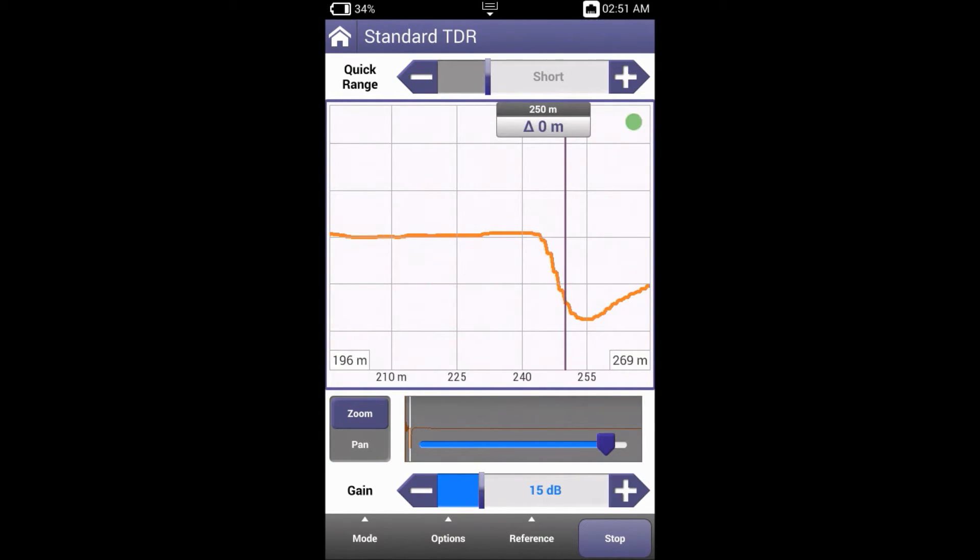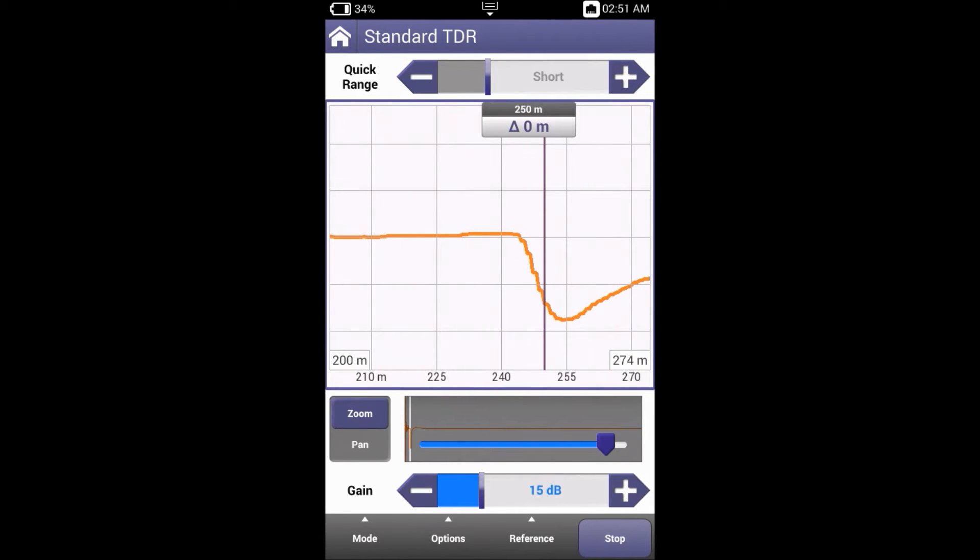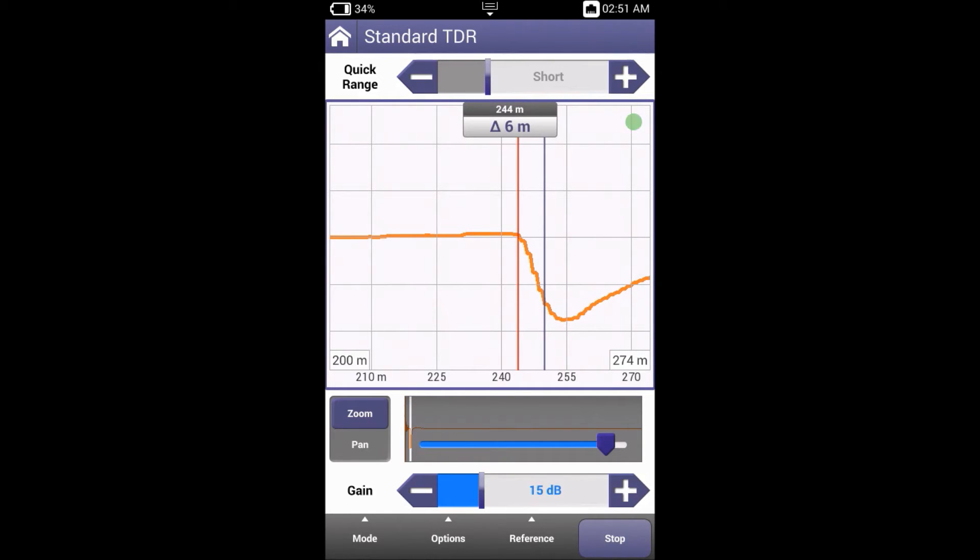To see this difference, we'll first zoom in and then press the marker button. Here you can see that a delta is being displayed. We can move this delta to the beginning of the dip. We can see that it's out by 6 meters, simply because the incorrect gauge was selected.